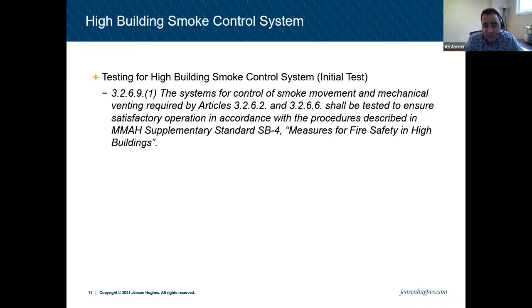So when you have all these measures, the OBC is asking for testing, and it's 3.2.6.9(1). A system for control of smoke movement and mechanical venting required by 3.2.6.2 and 3.2.6.6 shall be tested to ensure satisfactory operation in accordance with the procedures described in MMAH Supplementary Standard SB-4. There are some techniques and testing requirements in SB-4 that need to be followed, and this is going to happen at the time of occupancy. This is the building code; we're not in the fire code yet. So the building code is asking for an initial test, and the test result needs to be available at the time of occupancy. Once we have the satisfactory operation of the system, the building can be occupied.